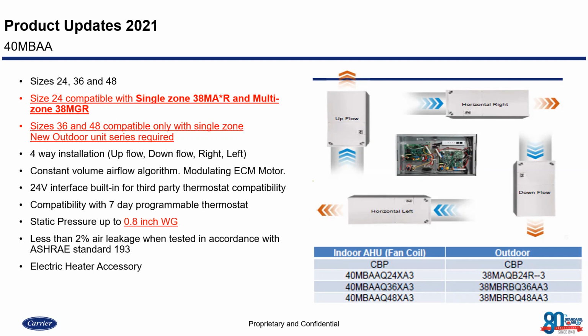This vertical fan coil offers 4-way installation, so we can do an upflow, downflow, horizontal left, and horizontal right. Now, the configuration is going to determine whether you need to remove the coil out of the cabinet and then reconfigure it properly, depending on whether you're doing horizontal left or right. That information is noted in the installation manual for how to take apart that coil and get it out, and then properly insert it back so that it is configured properly for the application.